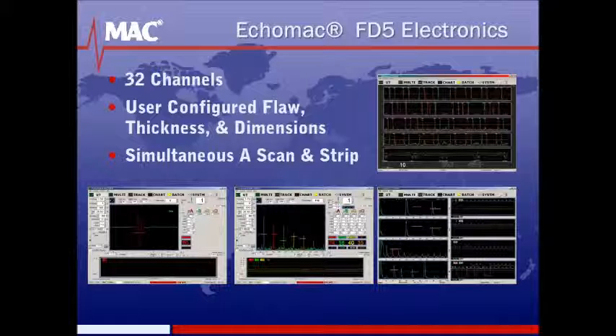The FD5 Electronics has a user-configured flaw detection or thickness gauging for each channel. It features 4 independent flaw gates in each ultrasonic channel, simultaneous A-scan and strip chart display of up to 32 channels, and adjustable pulse firing sequence to avoid crosstalk in multi-channel applications. Full network support is now available for viewing and controlling the instrument from a remote desktop.